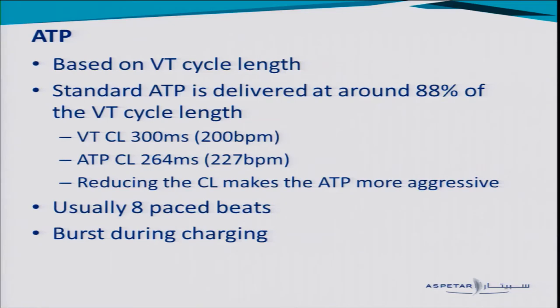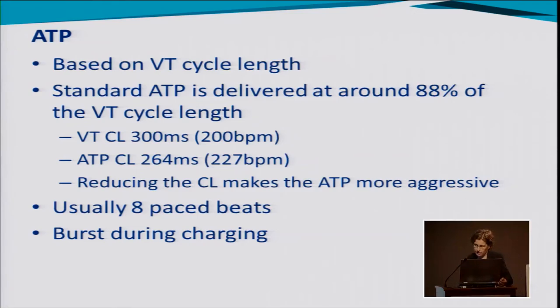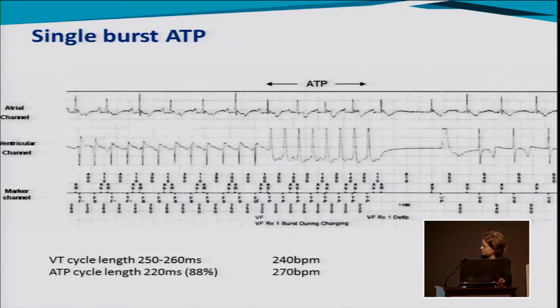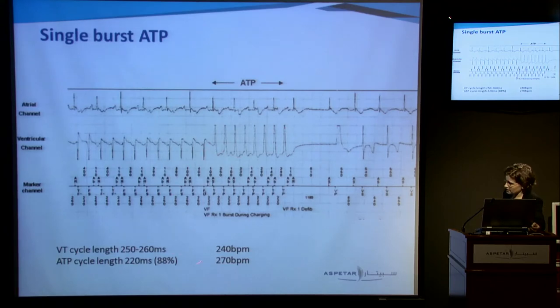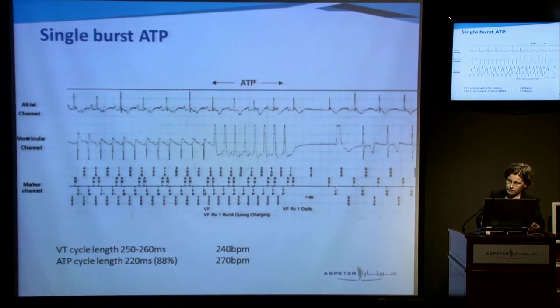Here you can see ATP in action: the patient goes into VT detected by the device, with a cycle length of 250 milliseconds — a VT rate of 240 beats per minute. ATP is delivered, eight paced beats at 270 beats per minute, which is 88% of the VT cycle length, and the cardioversion is successful — no need for a shock.